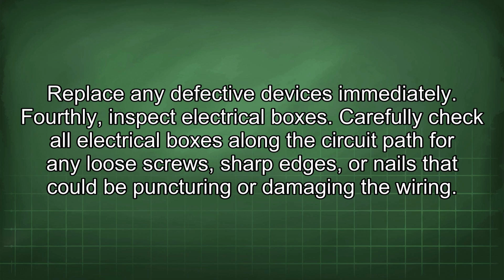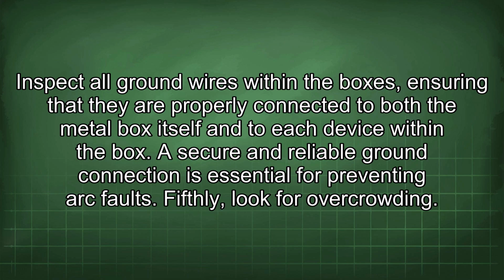Fourthly, inspect electrical boxes. Carefully check all electrical boxes along the circuit path for any loose screws, sharp edges, or nails that could be puncturing or damaging the wiring. Inspect all ground wires within the boxes, ensuring that they are properly connected to both the metal box itself and to each device within the box. A secure and reliable ground connection is essential for preventing arc faults.